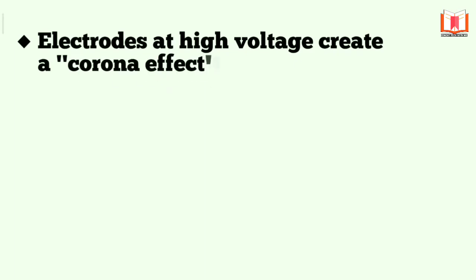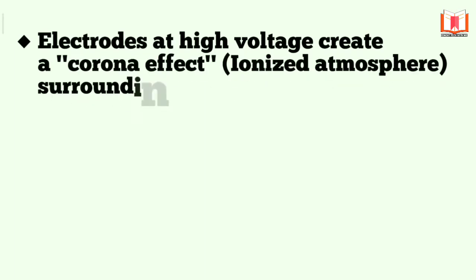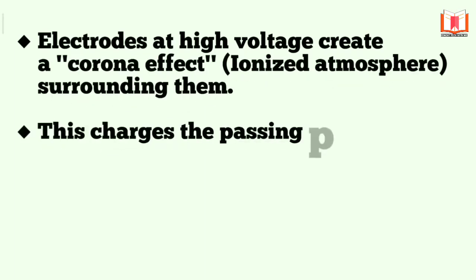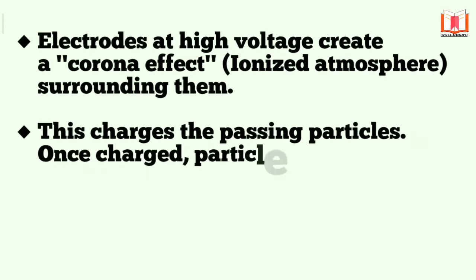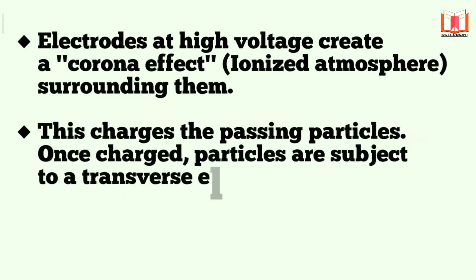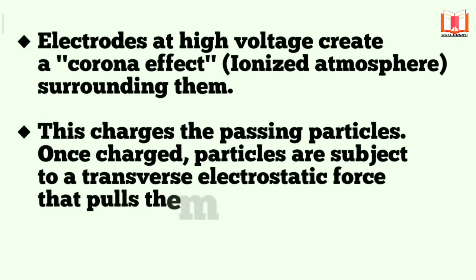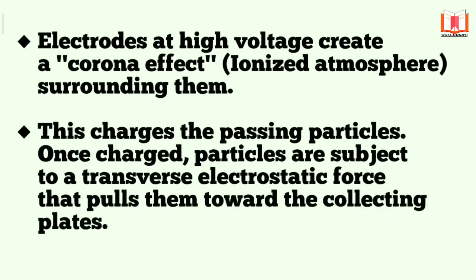Electrodes at high voltage create a corona effect, an ionization atmosphere surrounding them. This charges the passing particulates. Once charged, particles are subject to a transverse electrostatic force that pulls them towards the collecting plates.